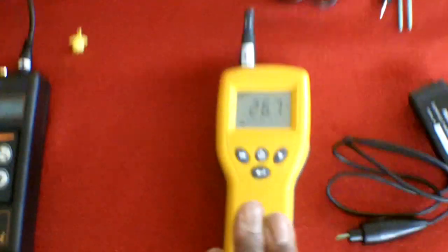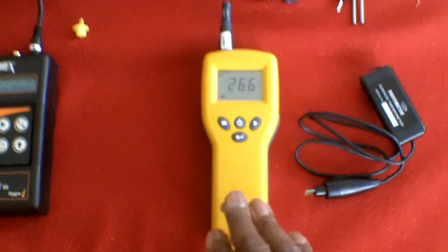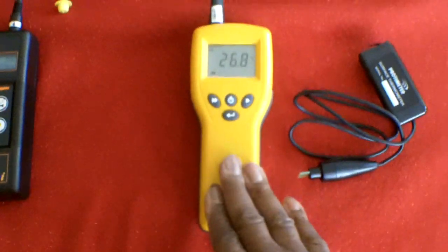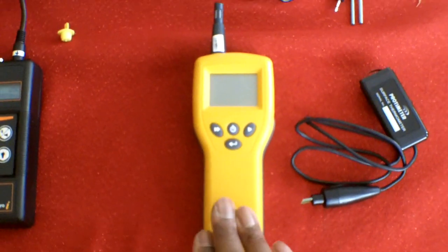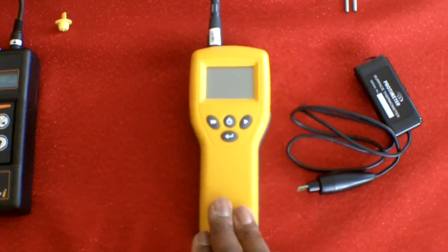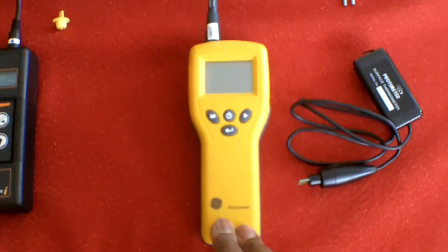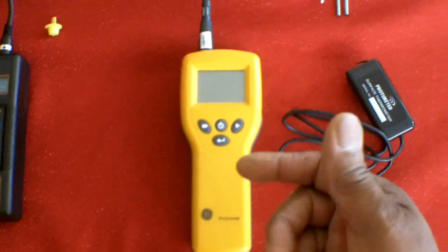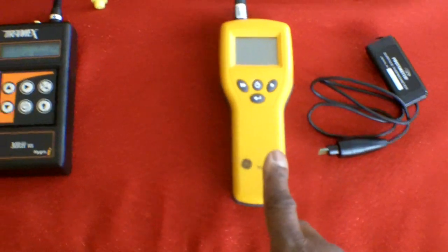Now, there's been a lot of criticism with these, because sometimes you'll get building surveyors that come into a building and they'll have one of those, and they'll put this attachment in and start jabbing the wall. Now, these are only calibrated for timber, nothing else. So the readings that you get from these are going to be quite, let's say, general, yeah? I could go into detail about radio waves and how they work and everything else like that, but basically this is what a lot of people use on brickwork and everything else, and even I was using it.